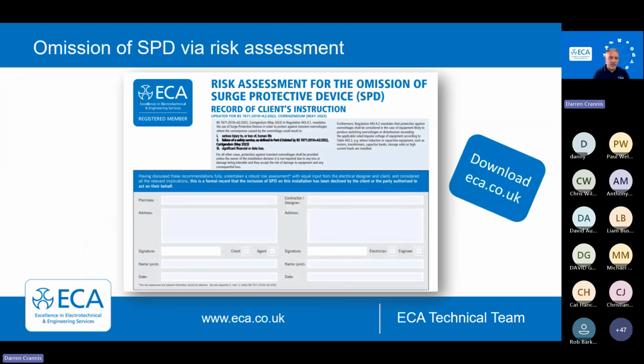Installations now are looking for voltage or overvoltage control, so they're looking at SPDs for that. But where it's risk assessed that they're not required, you've got a record of the client's intention here. So if your client doesn't wish for SPDs, we've got an ECA model form where you can document that, and you can put it with your electrical certificate as evidence.